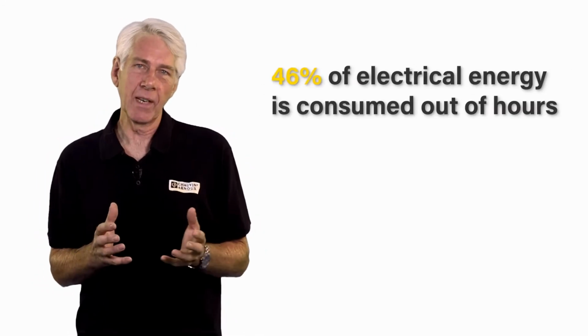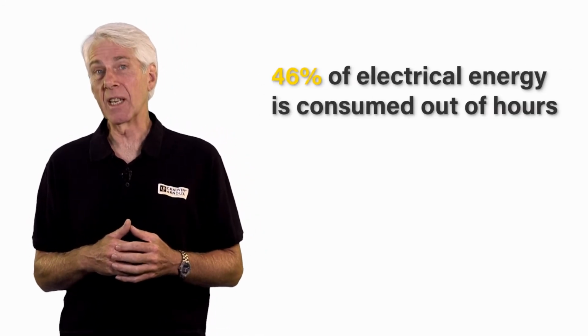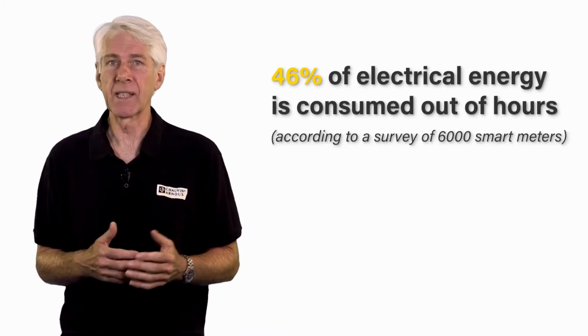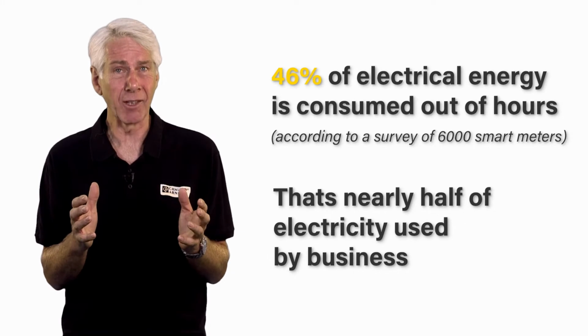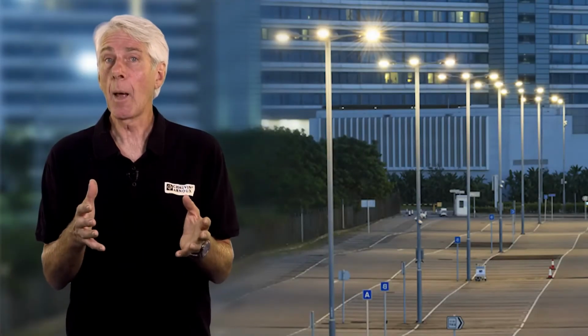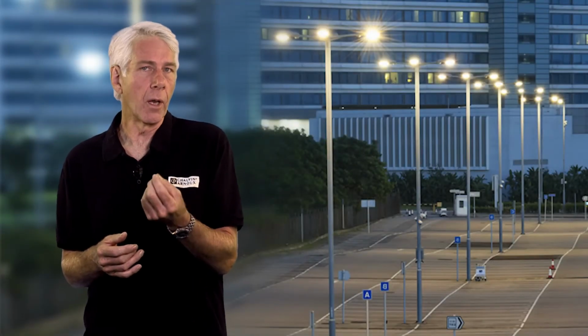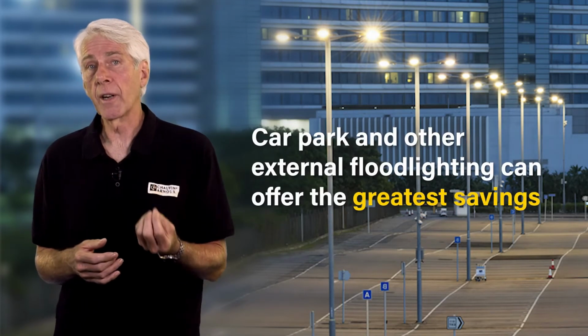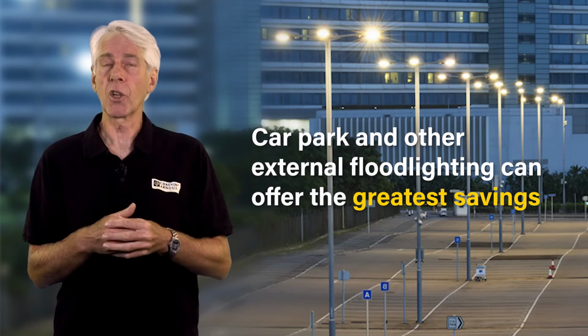Shockingly, 46% of the electrical energy used by UK SMEs is consumed out of hours, according to a survey of 6,000 smart meters. That's nearly half the electricity used by a business. One of the most common causes is office lighting left on at night and weekends, something you can often see for yourself as you travel around at night. Similarly, car park lighting. Being outside, it's often overlooked. Car park and other external floodlighting can sometimes offer the greatest cost-saving opportunities. Halogen floodlights can be replaced by LED equivalents, and the use of occupancy and daylight sensors will ensure that no energy is being consumed unnecessarily.